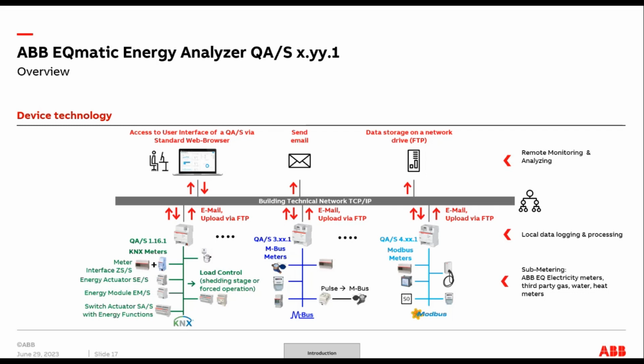For gas, water, and all that sort of stuff, you may have to put a pulse counter in the middle that will take all the pulses from your meters, convert them to MBus, and send the information to the meter. Lastly, on the left-hand side, we have our KNX devices that can take the information from all the KNX meters and KNX devices, implement load shedding, and then share this information back onto our network.